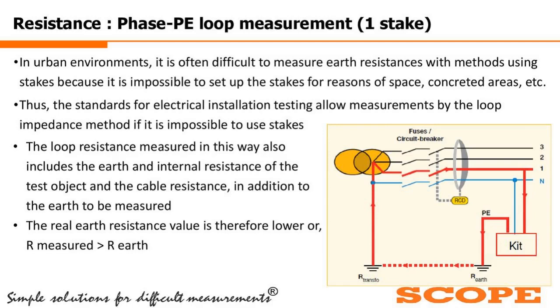Now coming to the resistance measurement, phase 2 with single phase to phase earth loop measurement, single stake. In an urban environment, it is often difficult to measure the earth resistance with methods using stakes, because it is impossible to set up the stakes for reasons of space, concrete zones or concrete roads, areas, building, etc.